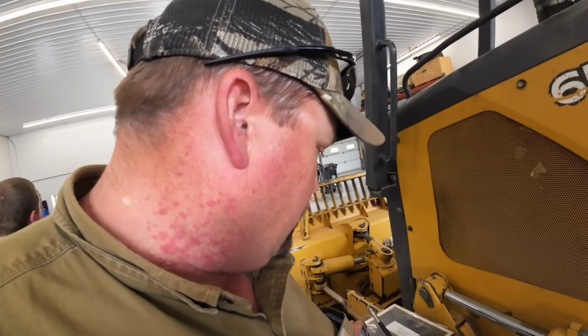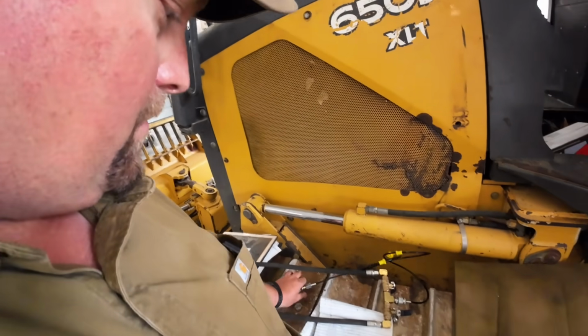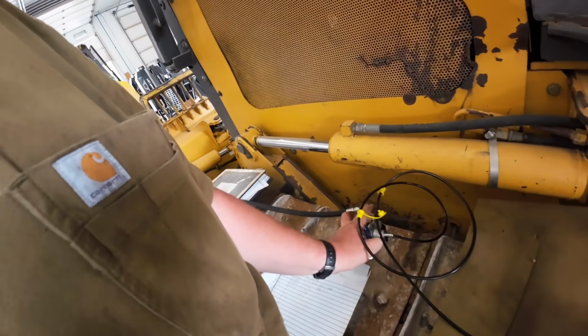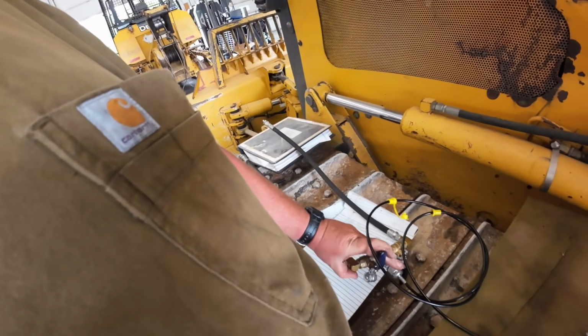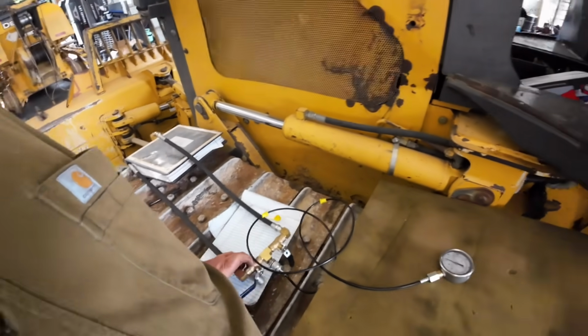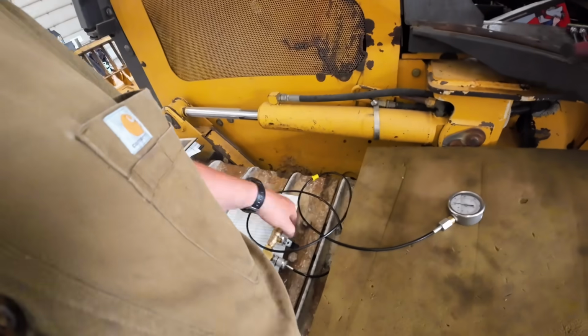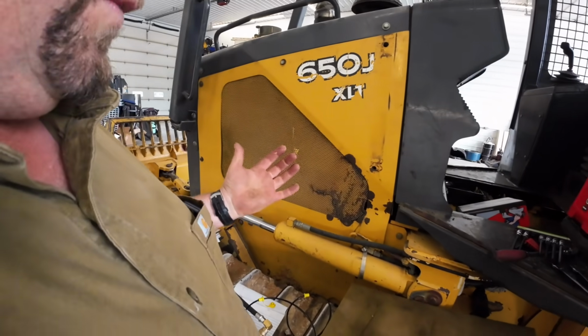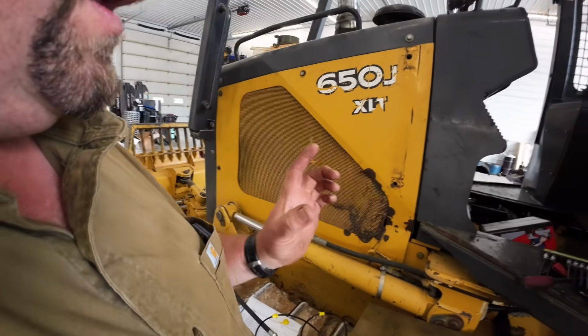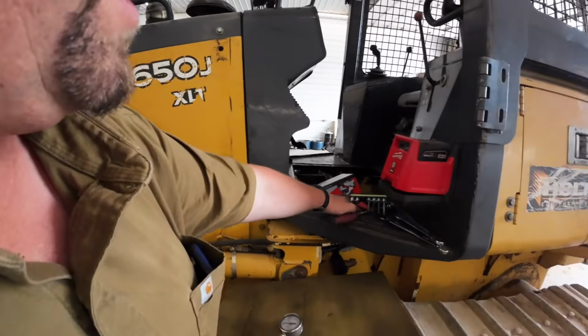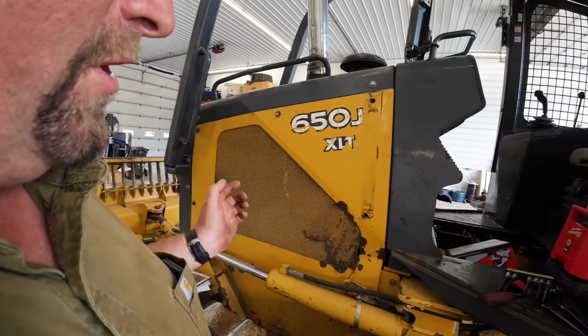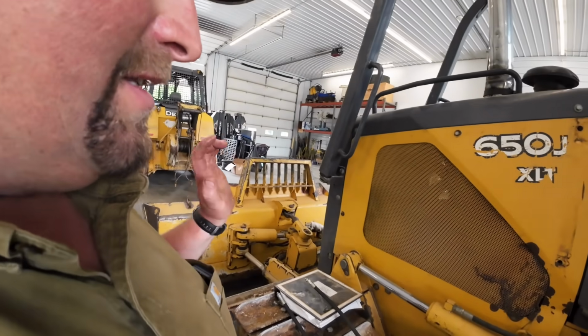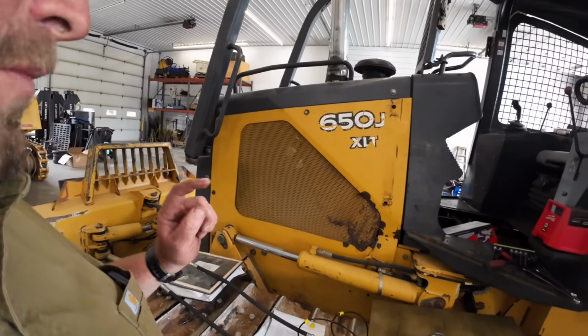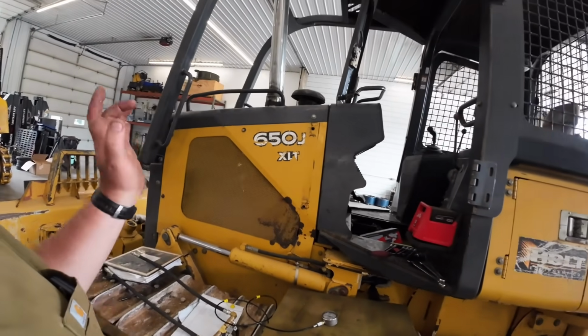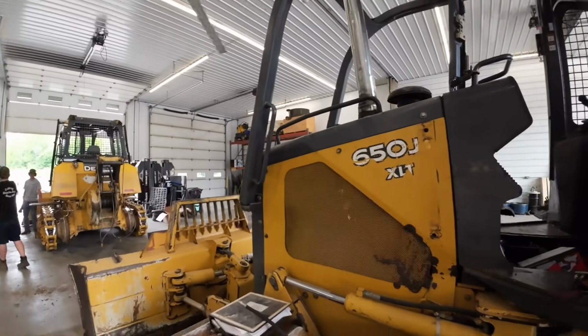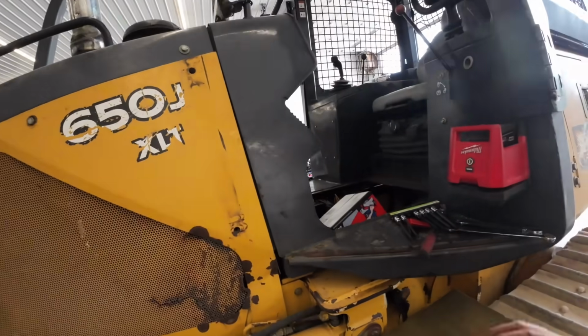So it has to be 5 psi or less. So I've got a gauge here, we'll go down these two ports. I'll show you guys, got a gauge plumbed up into the center. If you notice, I got two shutoff valves here. So what we'll do, we'll open one side up, that's going to send the pressure up to the gauge, say it may be at 250. We'll then shut that one off and open this side up. If it's more pressure, it's going to go up more. If it's lower, it'll drop down to 240 or whatever. So there's a little balancing thing in there, we'll have to take a small Allen wrench and adjust it until we get that differential sitting pretty much at zero - zero, one, or two PSI. But if it gets at six PSI, it throws a code and won't let you calibrate it till you get that fixed. If you get all that fixed, we'll go back through all those steps again, and hopefully it works. So we'll jump up here and show you where those adjust at.